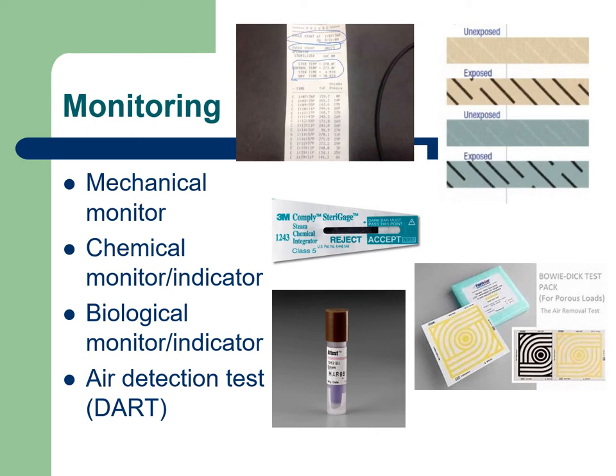This Bowie-Dick test is run in every single sterilizer in the department every day. Typically early in the morning, whoever comes in on first shift is going to run the Bowie-Dick test before we cook anything in those steam sterilizers. We want to make sure they're working properly. We want to put this in a very hard place that's furthest away from where the air is getting removed. So bottom front of the sterilizer a lot of times is where we will put this.